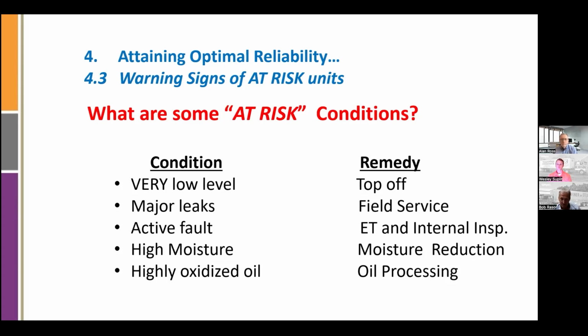We always recommend, regardless of furans, take a look inside. There could be something that we can adjust or fix, a tap switch, a loose connection. Electrical testing can confirm that further, such as your winding resistance, pointing out more carefully when you look inside what you can fix and cannot fix. Very high moisture is a problem, and we're going to get into moisture a little bit later, so I'll hold off on that. And then highly oxidized oil: you can stave off the effects of the acid that's created when that oil oxidizes by doing oil processing. Correct the oil, and try to get some of the acid-forming compounds out of the insulation with hot oil cleaning.